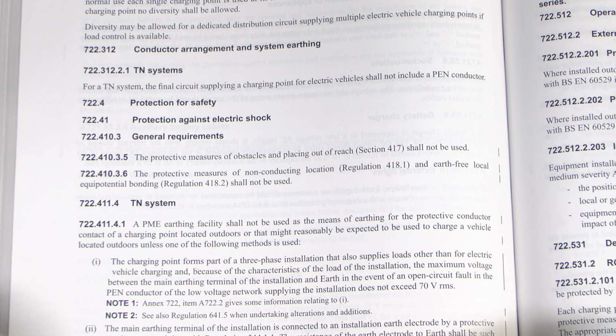Now, if it's a TNS system, which is essentially where you've got the separate conductor coming in, typically on an older sort of lead sheathed cable or whatever, then you can, and of course would, use the earthing point for that. So that's not really a problem there. And if it's a TT system, well, of course you're going to have to be using a TT system once again, which is the separate earth electrode in the ground. And of course the property is likely to already have one of these, and it certainly should do. You could install an additional one if required. Obviously depends on the condition of the existing one. So for TT and TNS, it's pretty much just using the earthing system which is already there. You don't really get a choice in the matter.